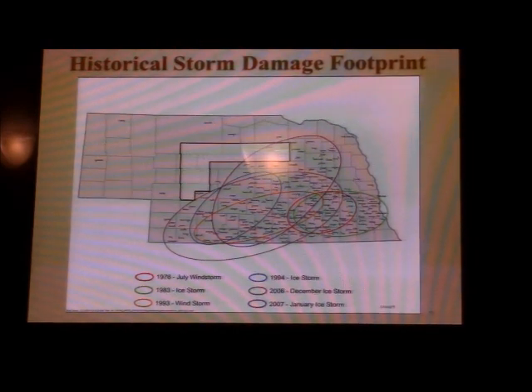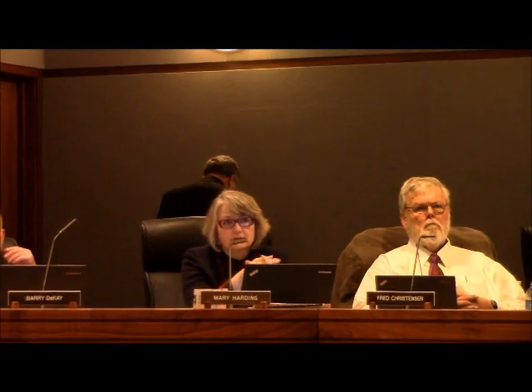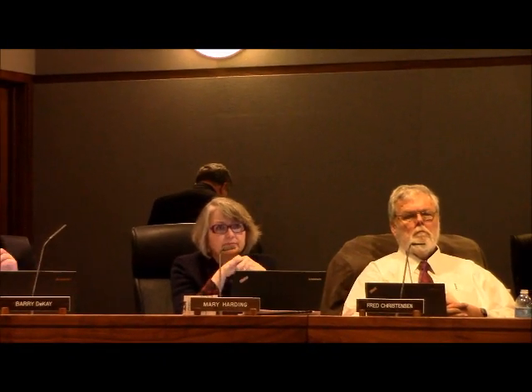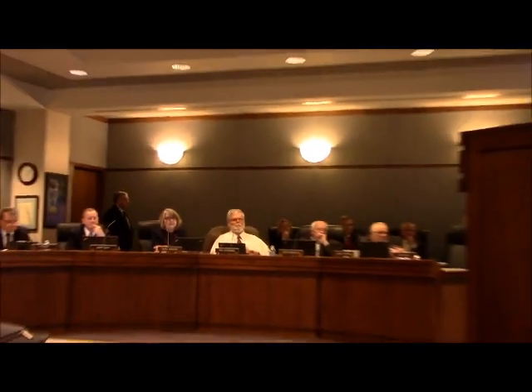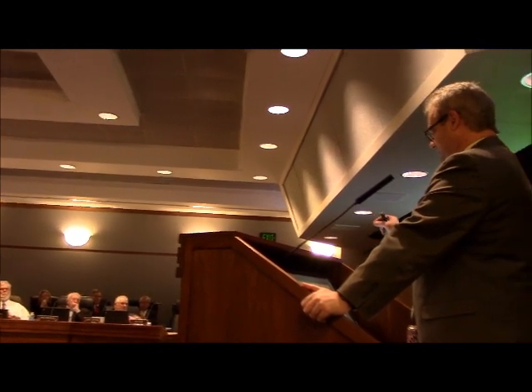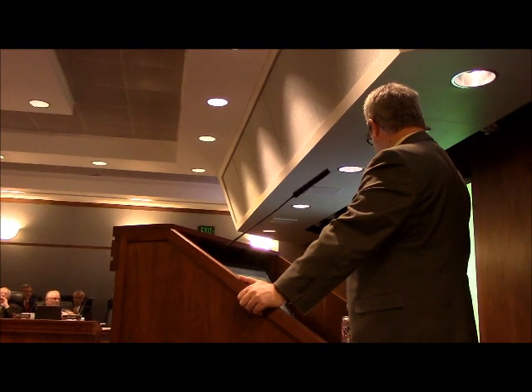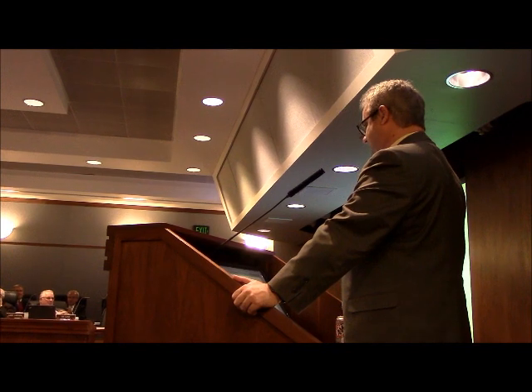Yes? Tom, one of the comments I received was that, well, you don't have a line up there, so of course you don't have storm experience up there. But what you're telling us is that that's not the case because we've got the 115 lines. Yes, we actually do have lines up there. Our customers have lines up there. And not only based on the experience of us and our customers, the people that write the codes that say this is what you should consider and how you should design your facilities to meet those codes recognize that there's a difference in icing and ice loading south and east of that versus north and west of that.